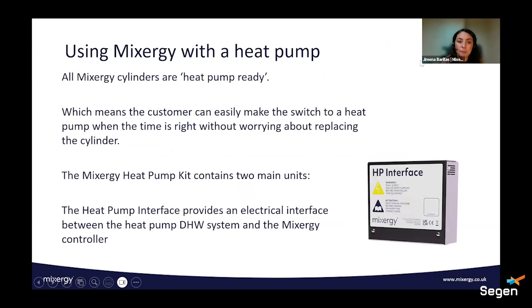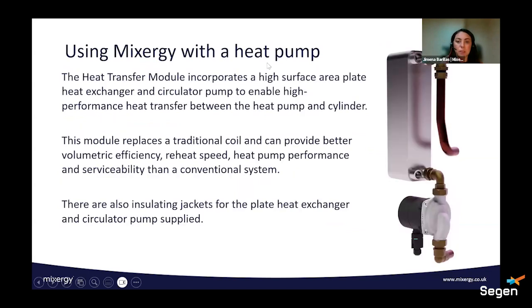Like I mentioned before, the cylinders are heat pump ready. They will need to purchase a heat pump kit, which includes this heat pump interface. This is what connects to any heat pump in the market. And then you have the plate heat exchanger. So the cylinder doesn't have a coil like they usually do. They will use this plate heat exchanger, which can provide better volumetric efficiency, reheat speed, heat pump performance, and serviceability. There's also an insulating jacket for the plate heat exchanger and the circulator pump supplied.